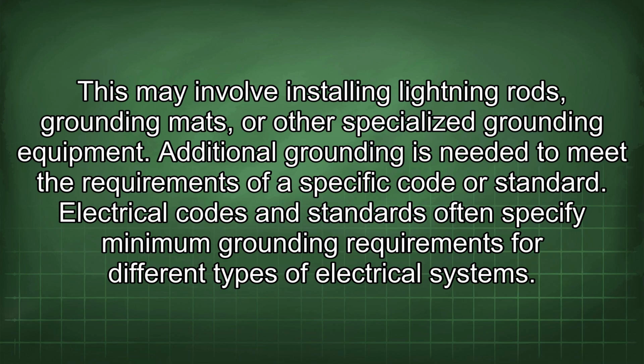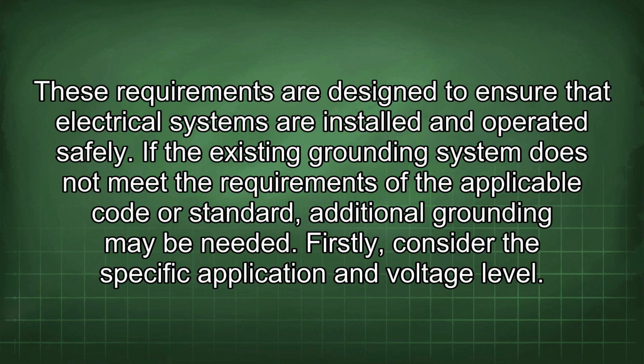Additional grounding is needed to meet the requirements of a specific code or standard. Electrical codes and standards often specify minimum grounding requirements for different types of electrical systems. These requirements are designed to ensure that electrical systems are installed and operated safely. If the existing grounding system does not meet the requirements of the applicable code or standard, additional grounding may be needed. Firstly, consider the specific application and voltage level.